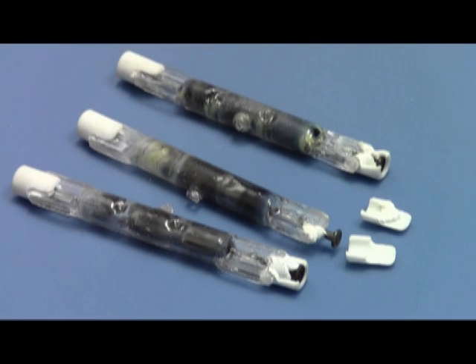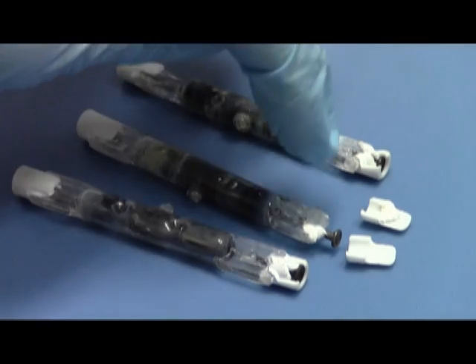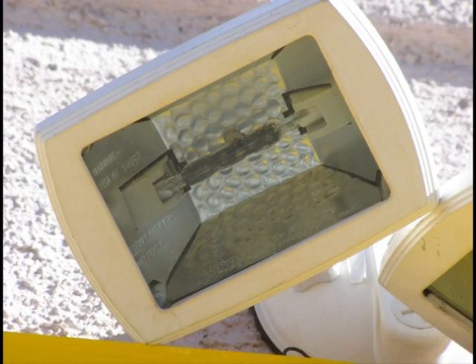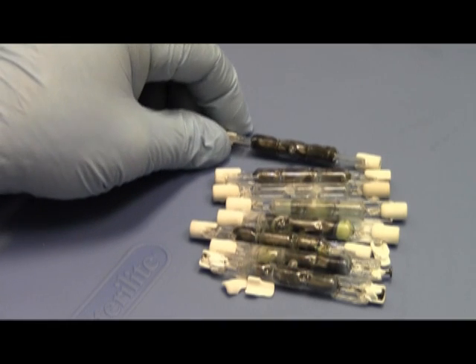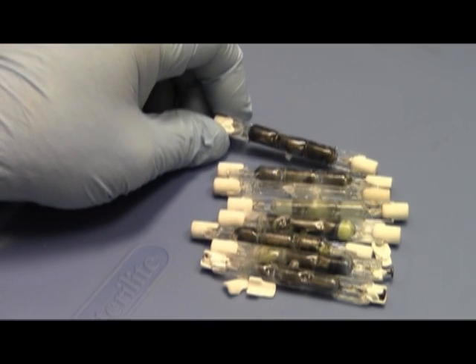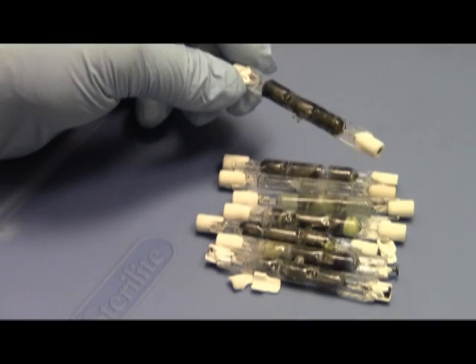The second cause of failure is that during installation, the porcelain end is handled too roughly. These bulbs are extremely fragile and must be installed with great care. In the third picture, you see a burnt light that is well within the tilt limit. In total, I replaced eight bulbs that had been replaced less than a week before. Let's take a closer look at these bulbs and determine the main cause of failure.